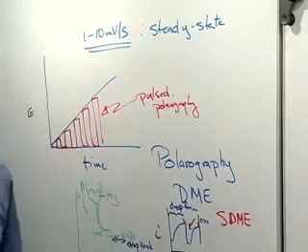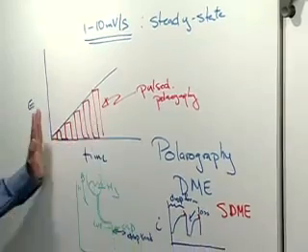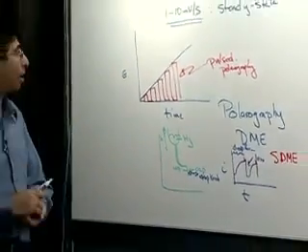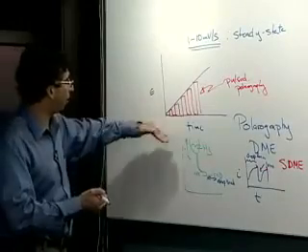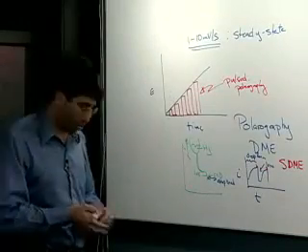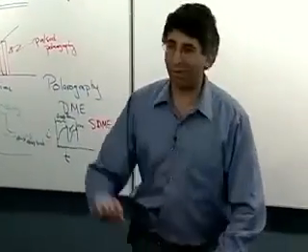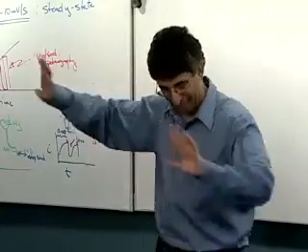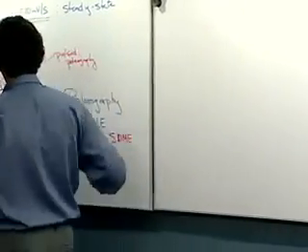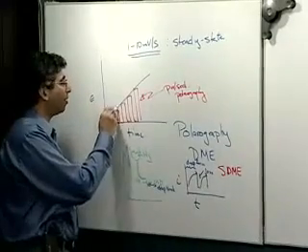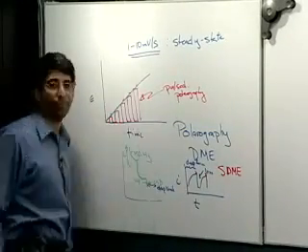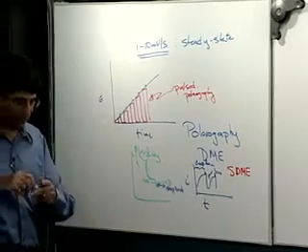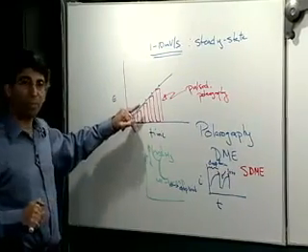And if I have a drop knocker, I can do this now because I can sync this waveform to my knocker, right? And so on a given drop, I can have the drop form, I can jump the potential, and then I can do sampled. If I try and look at the current coming out of that thing continuously with the drops falling off and this happening, forget it, I've got a total mess.